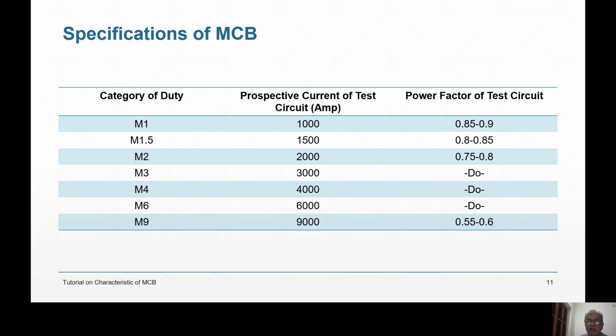And for each current, what should be the power factor of the test circuit? To maintain a particular power factor of the test circuit is also very difficult, because you have to break the current when the angle between voltage and current, phi, and cos phi accordingly, is this much. So that point-on-wave switching arrangement itself is very costly, right? Through all these things you have to pass, and then only you will understand what an important thing this small MCB is, which probably we are not even noticing.